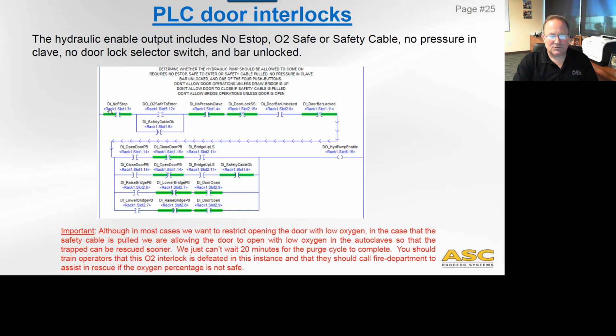And what you'll see here, which is a little different, is there's our bypass. And remember, I was saying that I'm going to allow the hydraulic enable to occur even with bad oxygen if there's a safety cable event. And so this is what allows us to open the door when a person is in the autoclave.